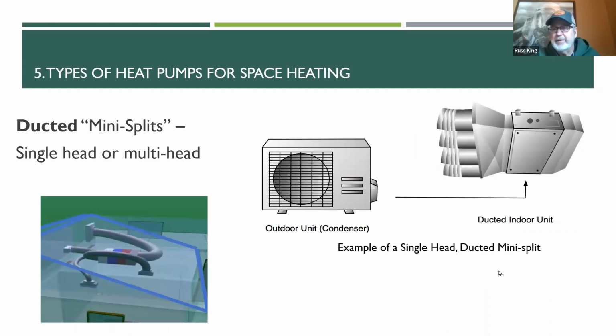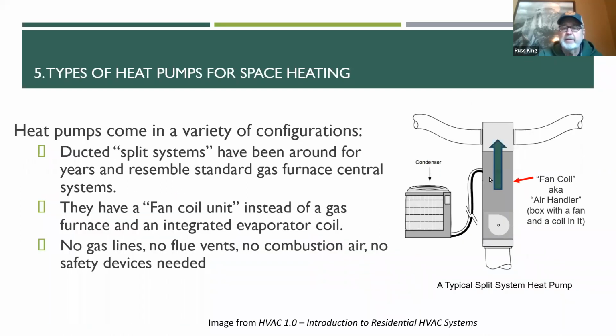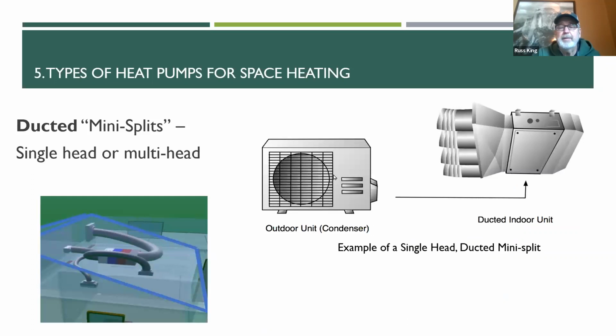Then the ones that are kind of the cool thing these days that you're seeing a lot of are called mini splits. Okay. They have a much smaller condenser. We call that a suitcase style condenser. The fan is blowing on a horizontal axis, as opposed to the more typical outdoor condenser with the fan in the top for basic air conditioners. Okay. They're smaller. They come in a single head or multi-head. So one condenser can actually serve multiple heads within the house.